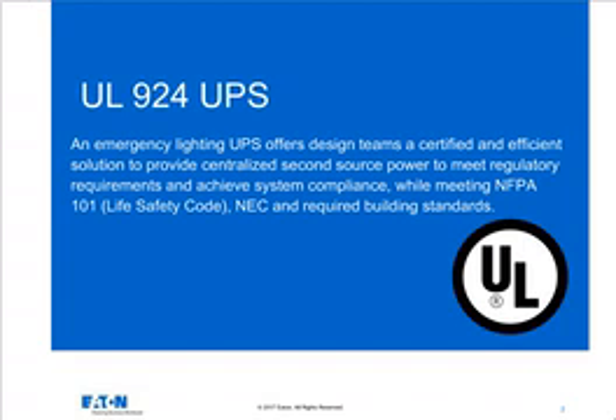So let's get a quick definition here if we push to slide 2, and a little description of a UL924 UPS. Now, UL924 is the listing or the standard that Underwriters Laboratory uses for UPS systems that are intended for emergency lighting. It should be understood that this particular type of system is only used for emergency lighting. In other words, if I have a UPS system that I'm using for data center backup or something along those lines, then I cannot use that same UPS as part of my emergency lighting backup system.